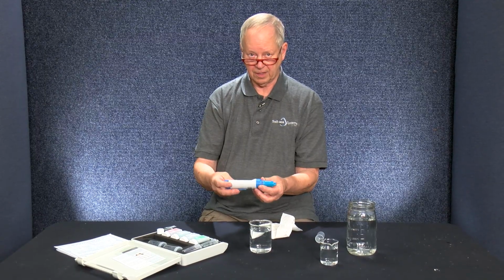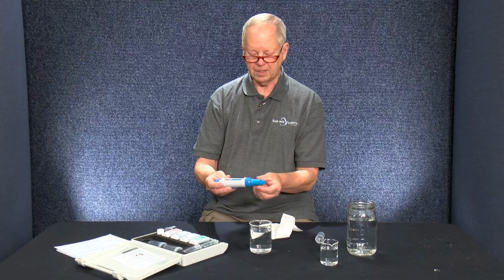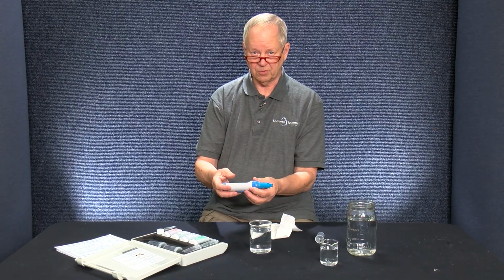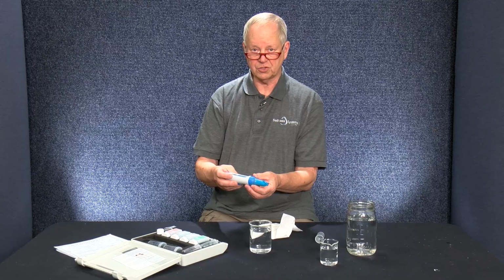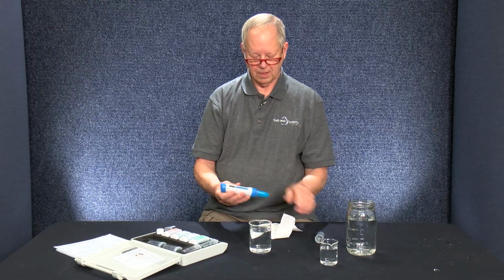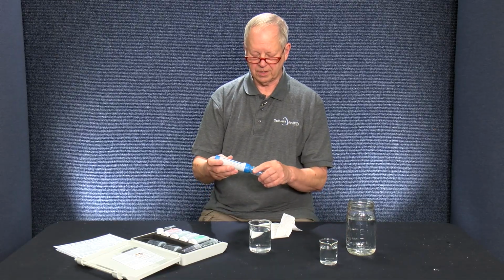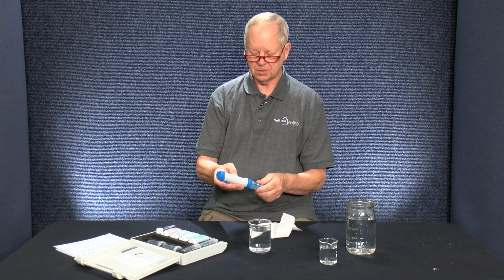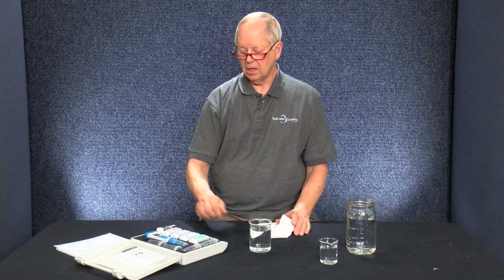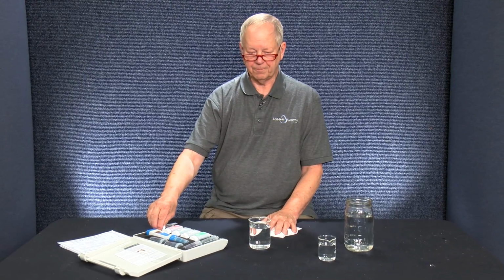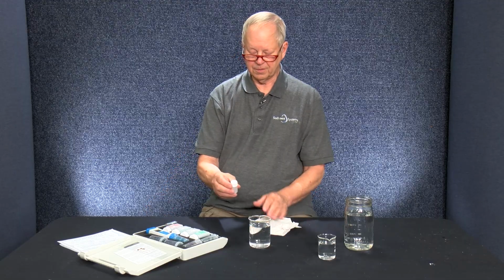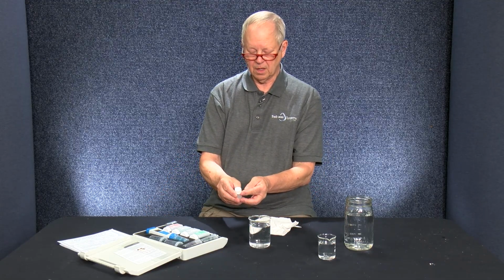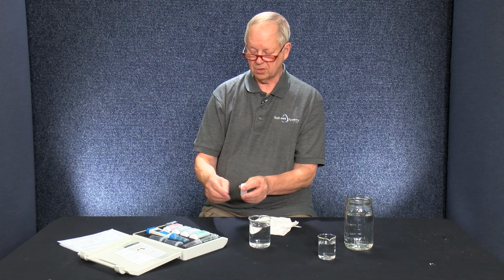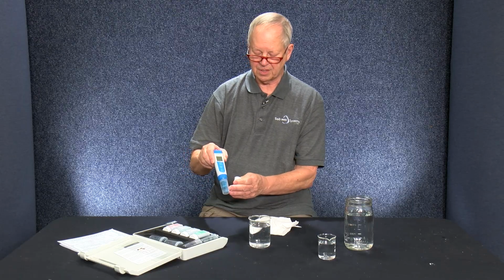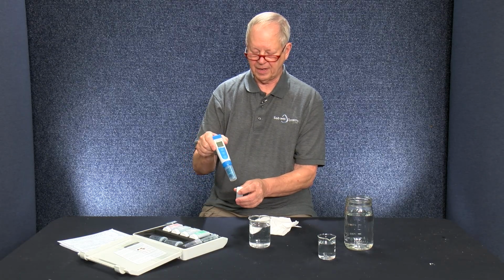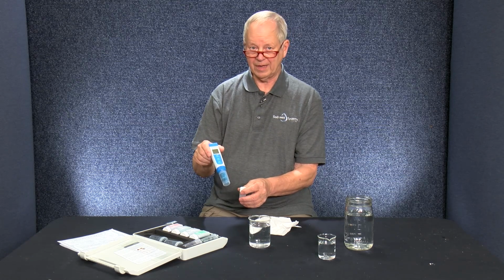Another thing about this particular meter is that the whole tip is replaceable. It screws on. You can get replacements, so in other words, you don't have to throw out your whole meter if your probes don't hold a charge. And to secure it, there's sufficient water on here. We can just put the cap on, shut the power off, and always return it into its case. For long-term storage, or if it hasn't been used in several months, there's this little bottle here of KCl solution. In this case it's sealed up. You would just put a couple of drops inside here, swish the probe around, and then dump it out, leaving a little bit in there. That'll preserve the probe or reactivate it after long-term storage.